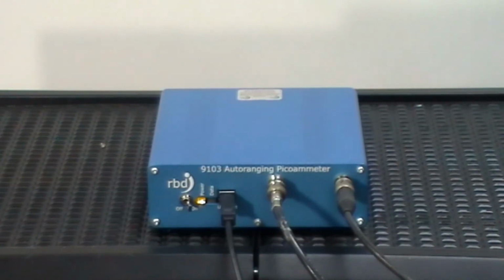Here the 9103 high voltage version is shown. Step 1 is we turn on the power switch on the front panel. The USB cable is connected to the PC. The HV connector connects to the high voltage source, and the input connects to the 9-volt current source inside of the test box that we made. That will be floated up to plus 5,000 volts DC.